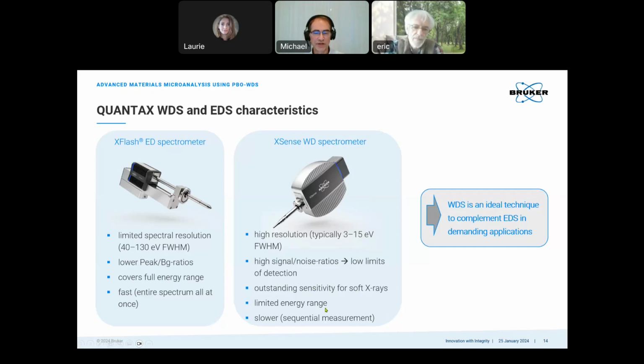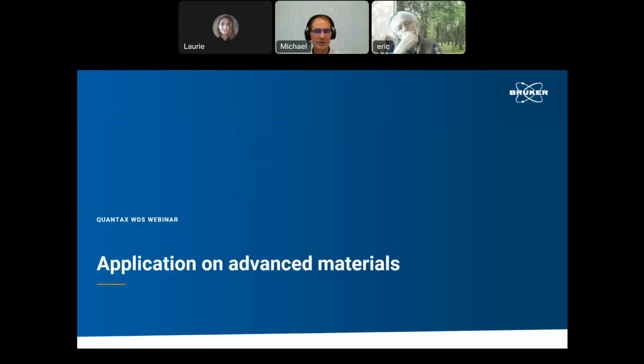The upper energy range is limited. The system is optimized for the low energy range, which makes some sense. And the measurement is slower since it's sequential, measuring one element after the other or one energy after the other. So a combination of both is the best solution. The WDS is an ideal technique to complement the EDS for demanding applications. And some of these applications will now be shown by Eric. And with this, I hand over to Eric.